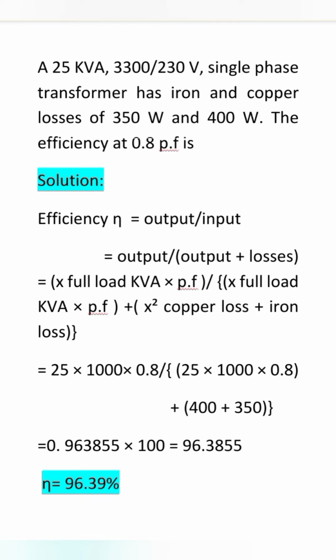We know the formula of efficiency: eta is equal to output by input. Substitute input as output plus losses. Losses consist of copper loss plus iron loss. So efficiency in terms of full load kVA is equal to x into full load kVA into power factor, divided by x into full load kVA into power factor plus x square copper loss plus iron loss, where x is the load of the transformer. That is, x is equal to 1 for full load, x is equal to half for half load, x is equal to 1 by 4 for quarter load, like that. So here they didn't mention the x value, so we take x as 1.